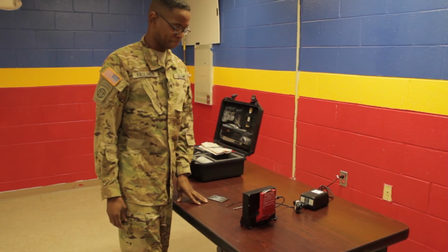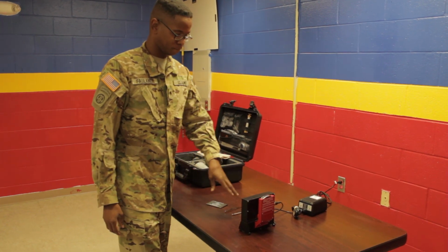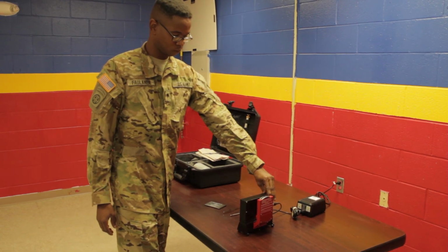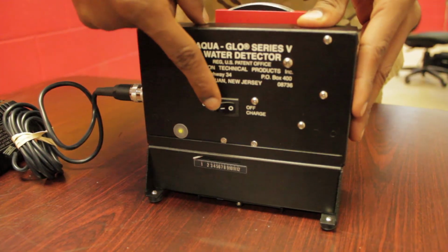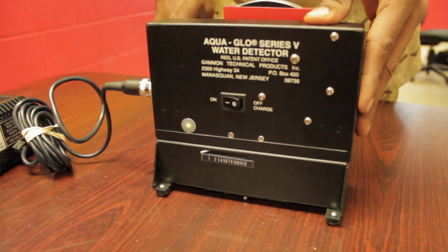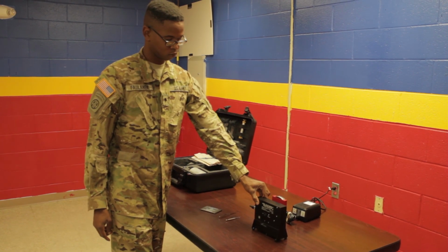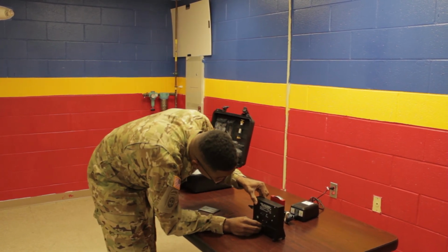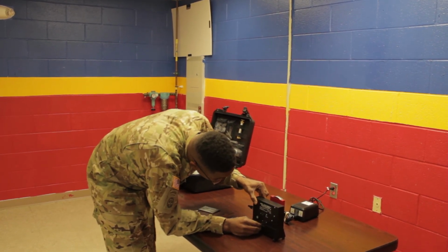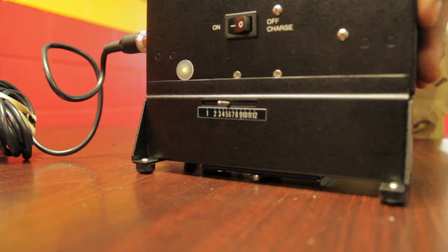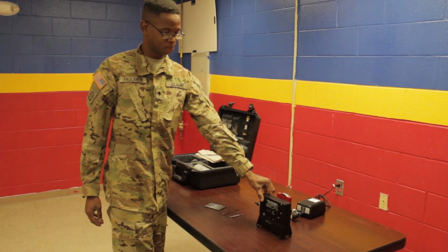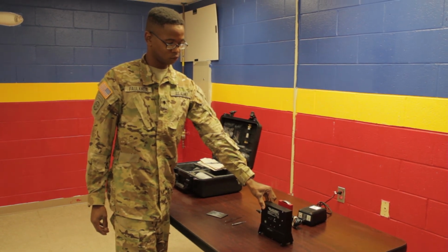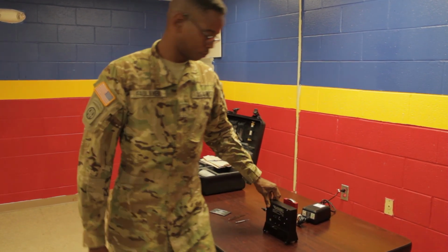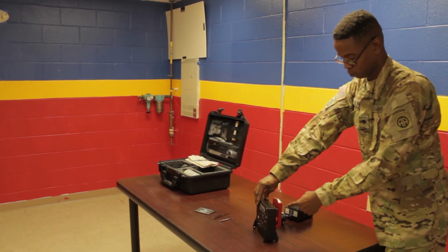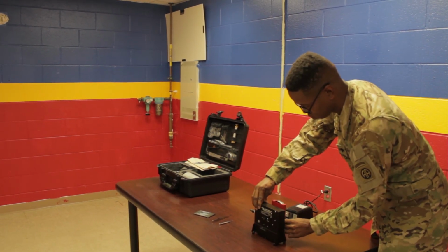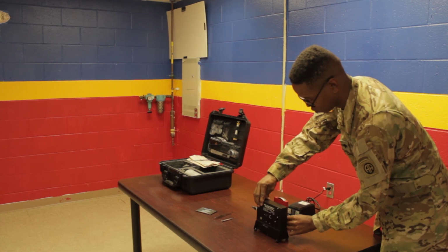Close the test area cover and place the test kit in its upright position. Turn on the water detector, setting the indicator switch to the appropriate power source. Position the light modulator lever located on the side of the water detector until the lever is directly above the number on the scale corresponding to the set number shown on the calibration pad. Depress the hooded button on the meter assembly portion and read the calibration meter. If the meter reads 0, the water detector is calibrated.